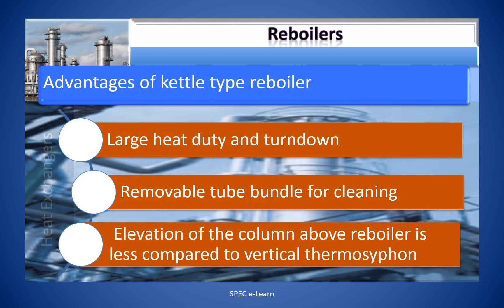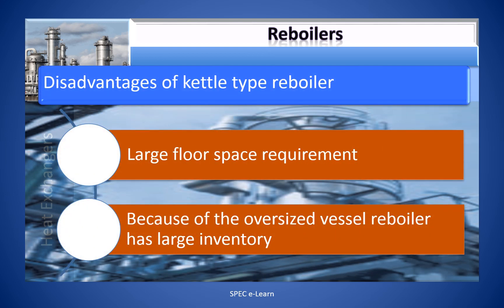The advantages of kettle type reboilers are: 1. Large heat duty and turndown. 2. Removable tube bundle for cleaning. 3. Elevation of the column above the reboiler is less compared to the vertical thermosyphon reboiler. The disadvantages are: 1. Large floor space requirement, i.e., plot area required is high. 2. Because of the oversized vessel, the reboiler has a large inventory of liquid.